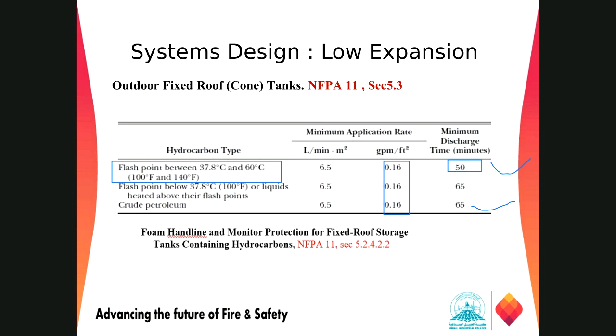Here we can see we have a flash point between 37.8 degrees Celsius and 60 degrees Celsius. The minimum application rate for this flash point is 0.16. So the rate is almost fixed for all the applications: 0.16 GPM per square feet of the surface. But the time required, for flash point between 37.8 degrees Celsius all the way to 60 degrees Celsius, is 50 minutes. And for crude petroleum, we need 65 minutes, and the same for other flash points.